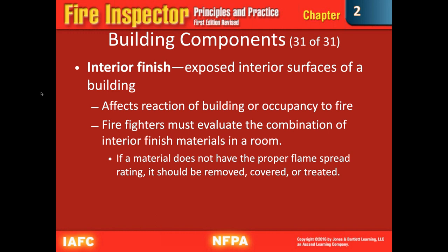All right. Interior finish refers to the exposed interior surfaces of buildings. So your gypsum board, if you have wood panel walls, if you got those 70s style wood panel or whatever, that's your interior finish. Considerations with this include whether the material will ignite easily, how quickly a flame will spread across the material surface, how much energy the material releases when it burns, and how much smoke the material will produce and what the smoke will contain.